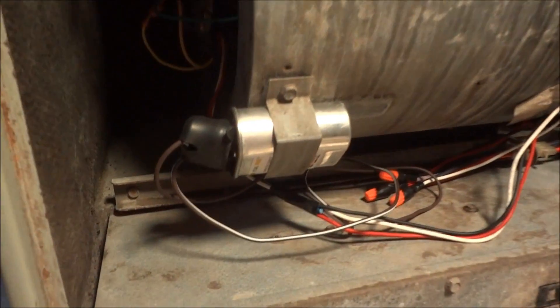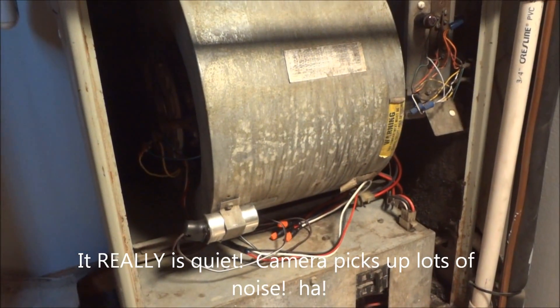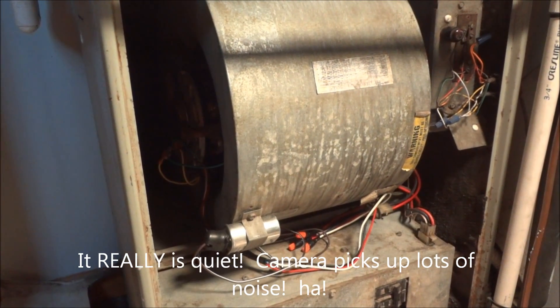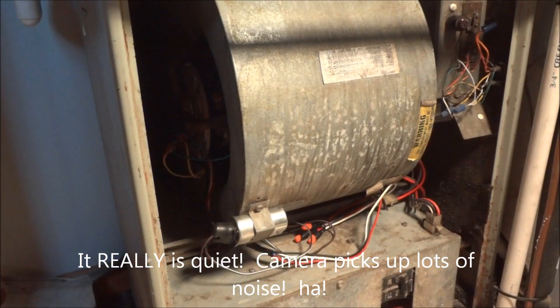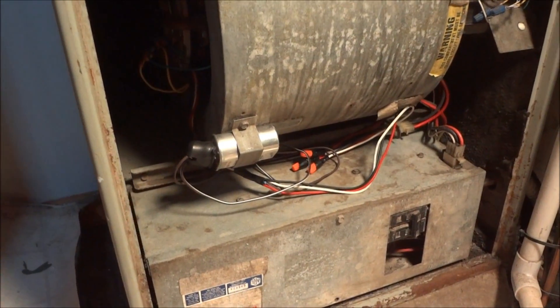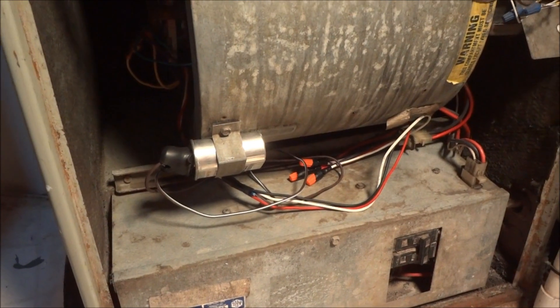It's all put back together with a new capacitor and a new motor — a very quiet running motor. Fixed for a hundred dollars. Good luck out there, hope you can fix your own. And it was cleaned up too, as best as could be expected for a 26-year-old unit.